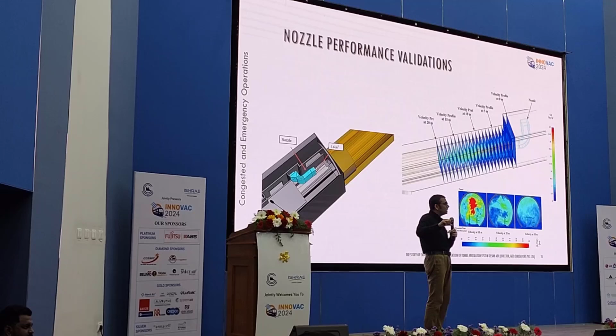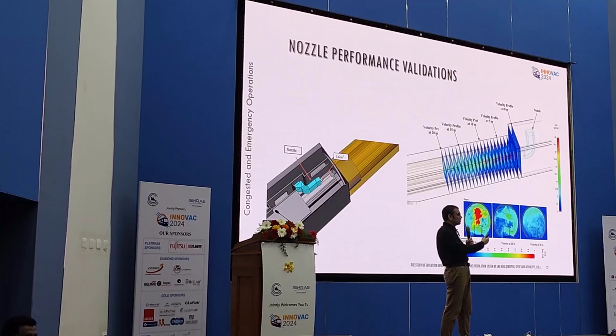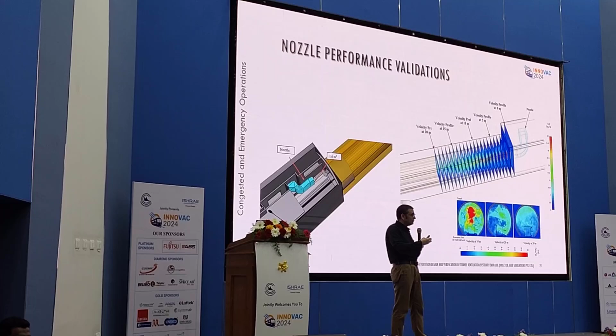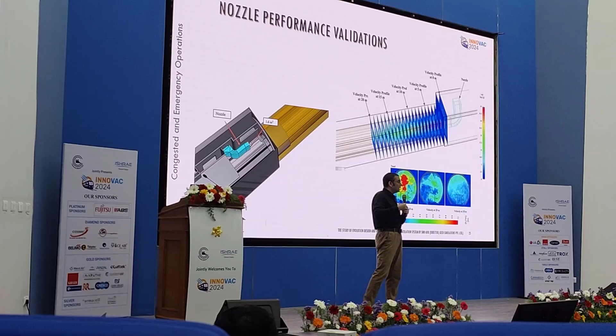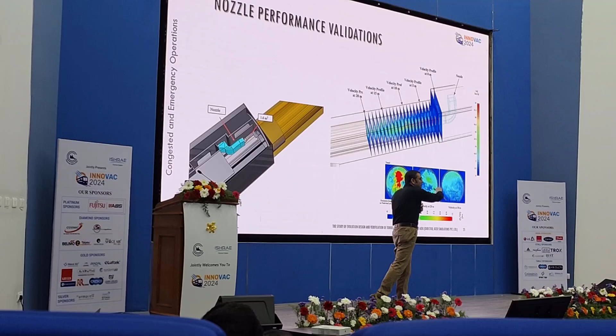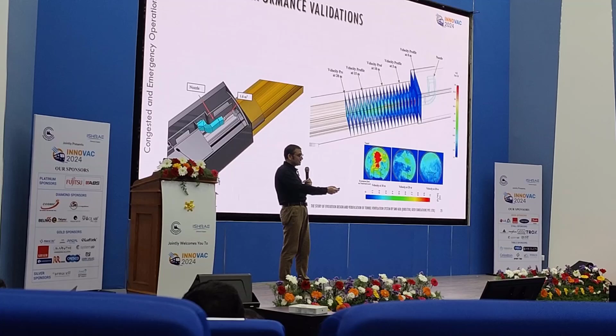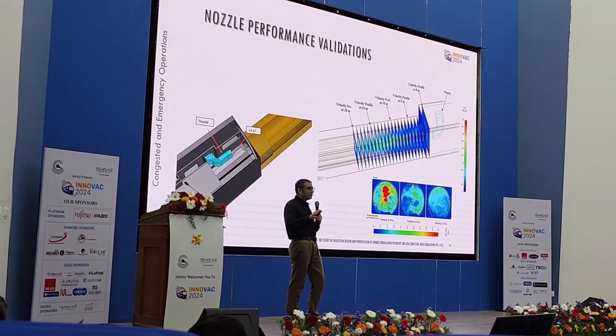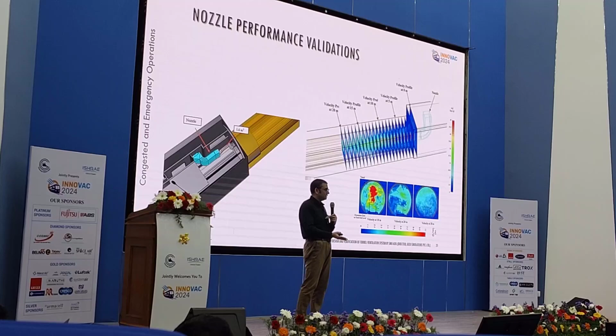This also covers the density differential, because in this pipe you're adding heat at a point and expanding a lot of air, and that expansion is scattered across the situation. If you supplied the same amount as you're extracting, it would create an overshooting condition, and the smoke would go to the next station, which we don't want. Therefore, we always extract more and supply less, and the current systems we build inherently do that.